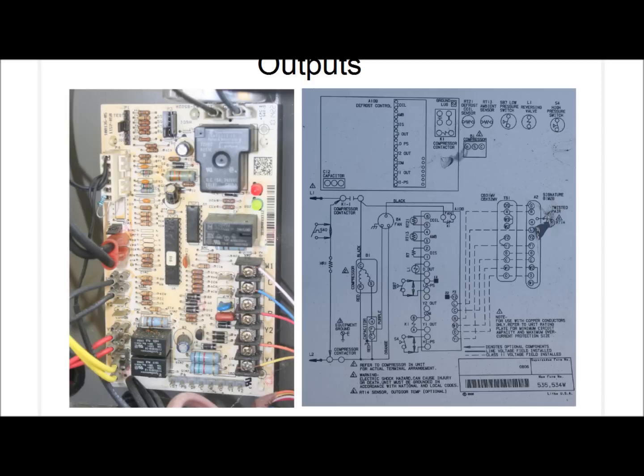Okay, a couple other ones that we need to look at, and that is right up here on the top left of the control board. These are indicated over here on the schematic, and they are the defrost coil sensor and the ambient air temperature sensor. And these just report back to the microprocessor what the temperature of the outdoor air is and what the temperature of the condensing coil is. So that is it for your defrost control inputs and outputs.